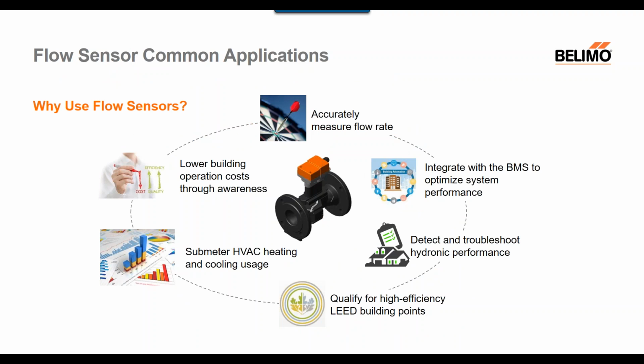So let's take a look at some of the flow sensor common applications. Why and where to use Belimo flow sensors? So, of course, to accurately measure flow rates. Also to sub-meter HVAC heating and cooling usage. To lower building operation costs through awareness. Detect and troubleshoot hydronic performance. And to integrate with the BMS to optimize the system performance. And last but not least, to qualify for high efficiency LEED building points.